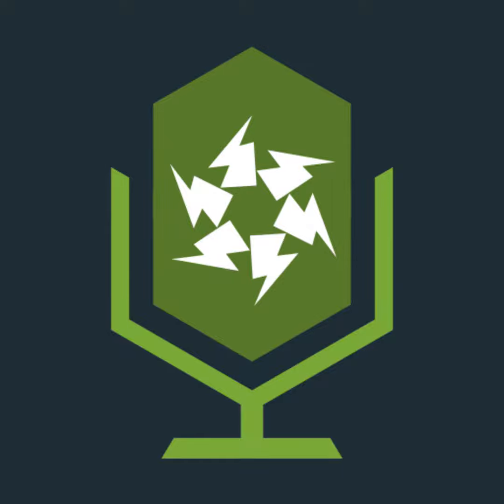So, preventing a current resulting from a fault from passing through the body of any person or any livestock, we have typically double insulation. If there is a single fault condition, there's another layer of insulation, so fault current will not find a way outside of that class of equipment to the person. Similarly with class 1 items, we'll have the ADS process. We'll have the earthing and the bonding present. We'll take that current away, removing that exposed live part.